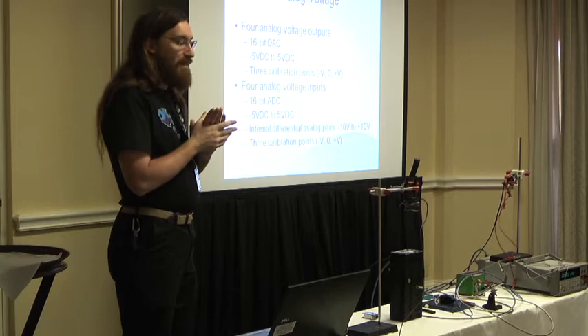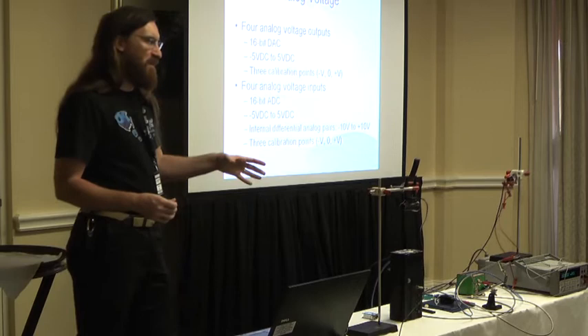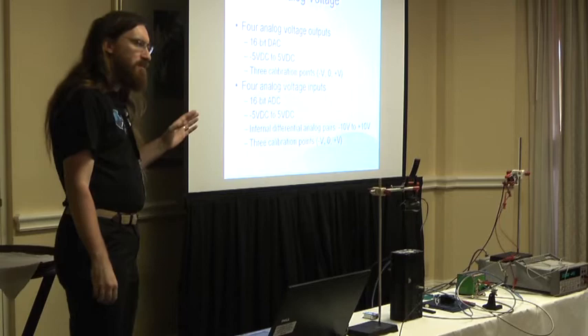Both of these can be calibrated, and it's recommended that if somebody gets one of these, they calibrate it for their system to make sure it's in agreement with all their other equipment — perhaps using a high-end multimeter. If you're only interested in the range from minus one to one volt, you can calibrate just on the outsides of that range and have very accurate calibration for that band.